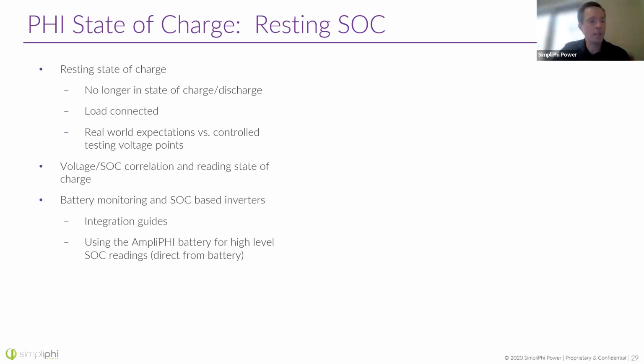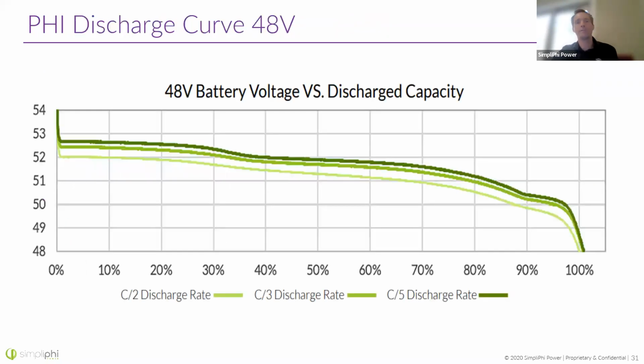A gateway is a piece of equipment that plugs into the communications of the battery, and through software, you're able to read individual statistics off of each SimpliPhi, including the larger SimpliPhi 4.98 kilowatt hour batteries. With those communicating batteries, we can get more information out of them.